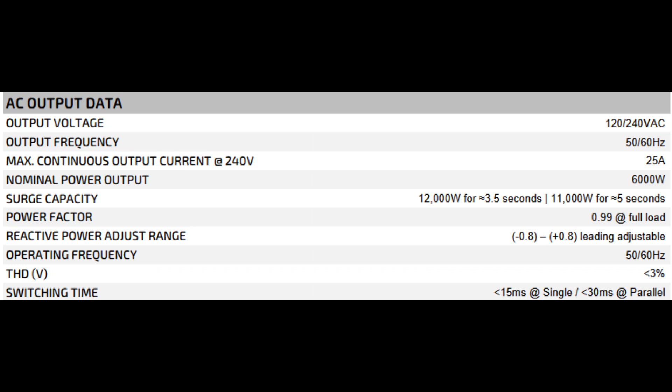Power factor at 0.99 means it's very efficient with minimal power lost to inefficiencies. Reactive power adjust is more advanced. In simple terms, if you need to correct the power factor for certain inductive or capacitive loads, you can tweak it. THD, total harmonic distortion, less than 3% means the output power is clean, which is great for electronics. Switching time below 15 milliseconds means that if your inverter switches from grid to battery, your devices shouldn't blink or reset.